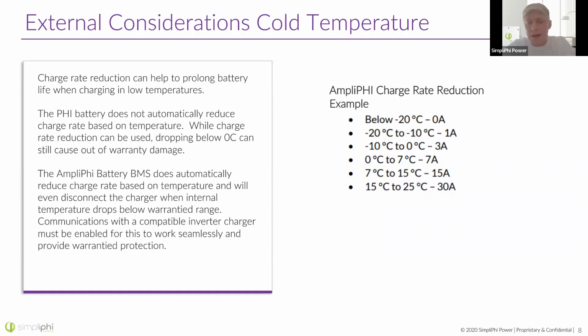The SimpliPhi BMS automatically curbs charging rates to what you see here on the right. For any installation or battery temperature below negative 20 degrees Celsius, it completely cuts off charging capability. From negative 20 to negative 10 degrees Celsius it allows 1 amp of charging, negative 10 to 0 degrees Celsius allows 3 amps, and so on. The BMS reports these values automatically to your inverter charger and asks that it reduce charging to those rates.